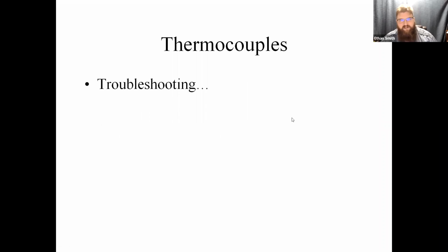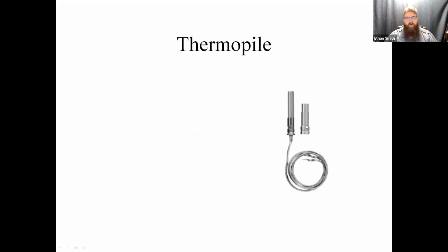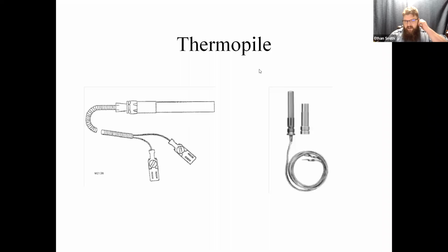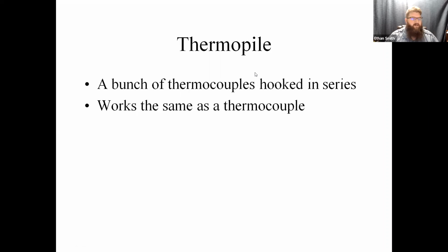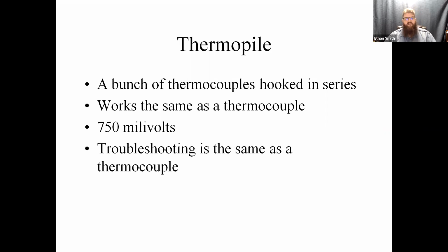If we need a little more voltage for something like a fireplace, we can use a thermopile, which is very aptly named because it's just a bunch of thermocouples jammed into a single housing. So it's a pile of thermocouples. These will range anywhere from 370 millivolts up to 700 millivolts, depending on what you're using them for. We'll use these to generate a little more power for larger gas valves or things like fireplaces. It's just a bunch of thermocouples all in series. Same troubleshooting as a thermocouple, though. Basically, you get it hot, it should generate electricity. If it doesn't, it's usually the hot junction inside that thermocouple that has failed, and it's time to replace the thermocouple.